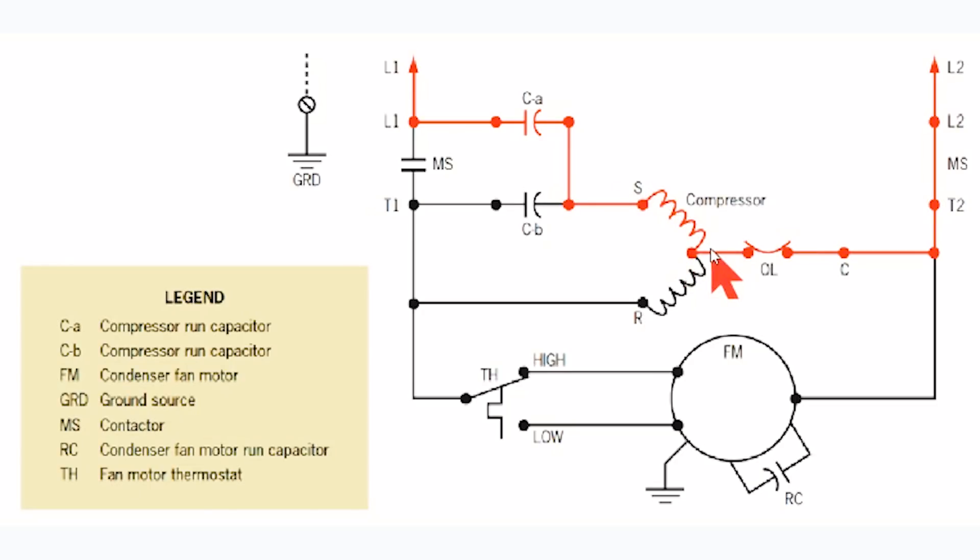But it's not going to get too hot, overheat, or draw high amperage because the amount of amperage that can go through this start winding is completely dictated by what can be stored in that smaller capacitor. This capacitor is acting like a little pressure tank that allows a certain amount to move in and out of that start winding - like a little trickle heater.